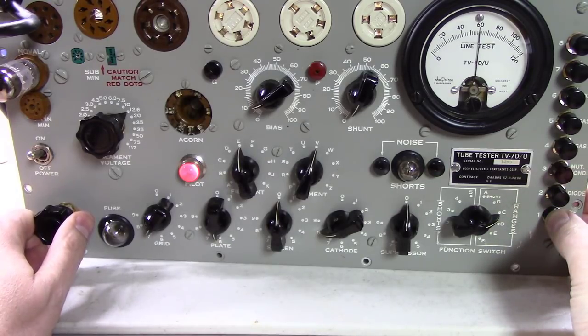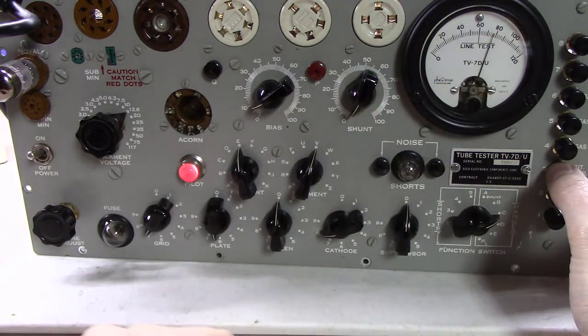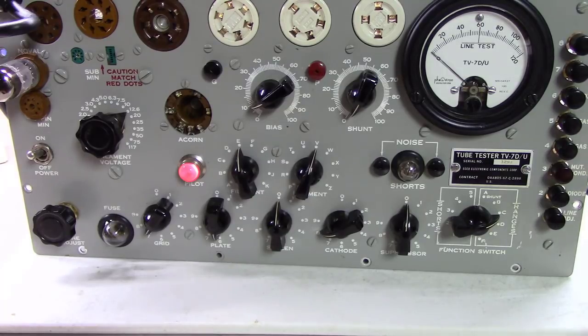So first thing you want to do is your line set, and then look. We're not quite at 80, and this thing's supposed to be 84. So we're going to go adjust R114 to get it to 84, because this will be more accurate than the old manual style that we just did a minute ago.